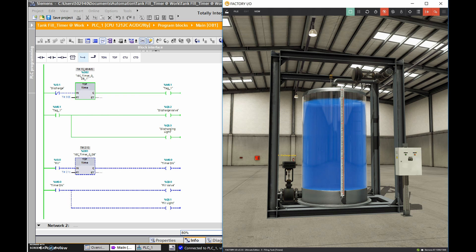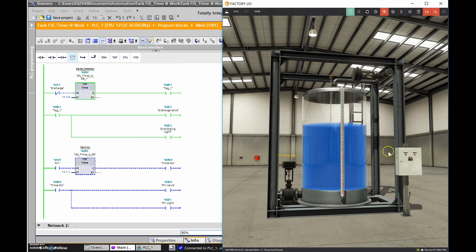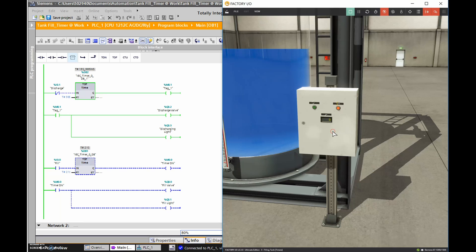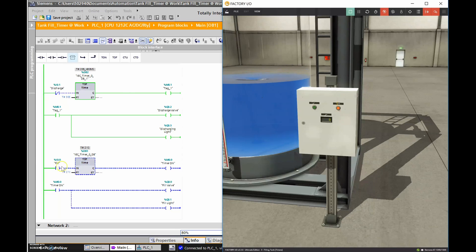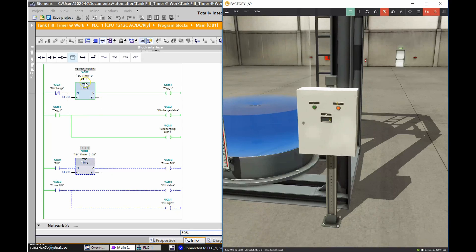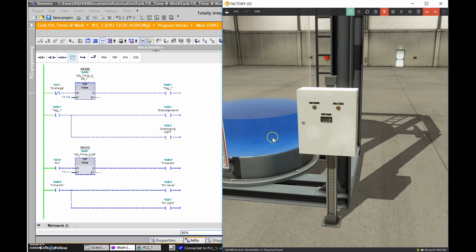Pressing the discharge push button illuminates the light and drains the tank. The second discharge has a longer timer value because when we get to that lower level there's very little head pressure remaining, so it takes a long time for that small amount of water to drain out - same as a capacitor where draining the last voltage out takes a long time depending on capacitor size and pipe resistance.